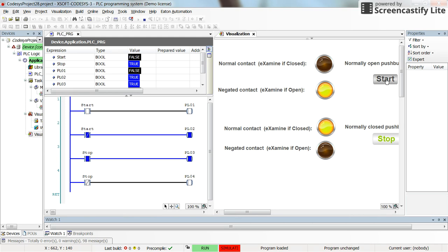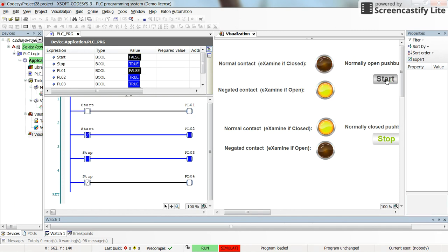But if I press the start push button, you can see that pilot lamp 01 will be turned on and pilot lamp 02 will be turned off. Why? Because in this case the contact is closed, so examine-if-closed gives us true and examine-if-open gives us false.